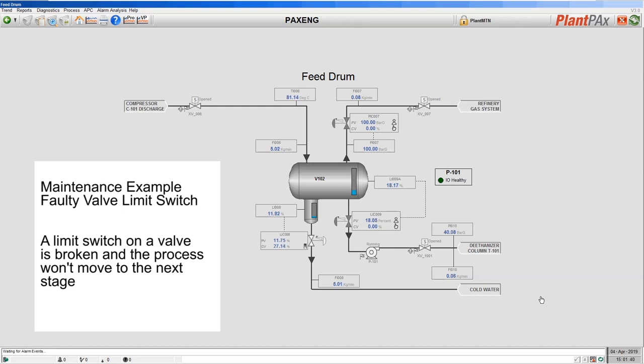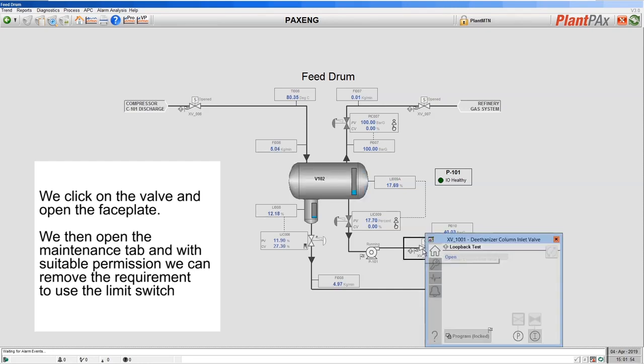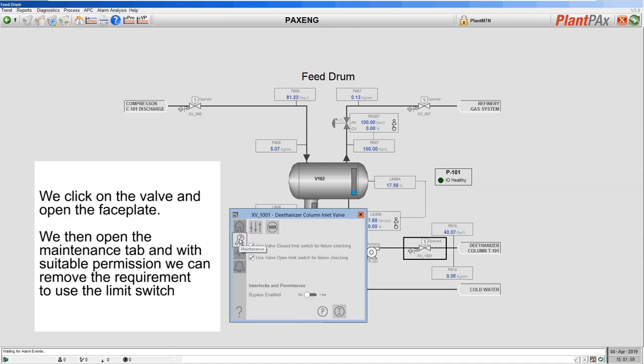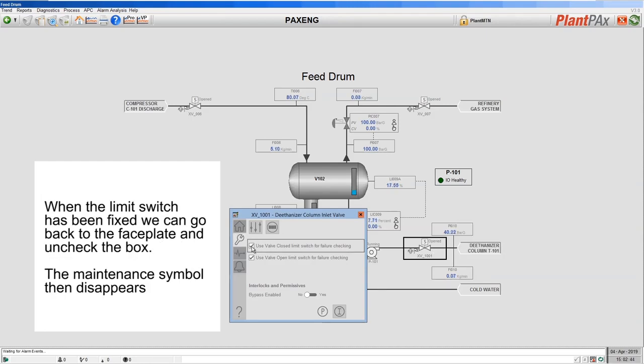In another example, let's say the limit switch for our valve has broken and we need to simulate it to allow our process to continue. I can do that from the faceplate by bringing up the full faceplate for the valve and going into the maintenance tab. I can decide whether the valve uses the actual limit switches or simulates them. By logging in with suitable permissions, I can select to simulate the closed limit switch, so it's no longer using the actual limit switch for determining if the valve is closed. Again the maintenance symbol is displayed to show something is not normal, and it's shown on exactly where the non-normal situation is. I can remedy the situation by selecting the box to use the actual limit switch value, and the maintenance symbol is removed.